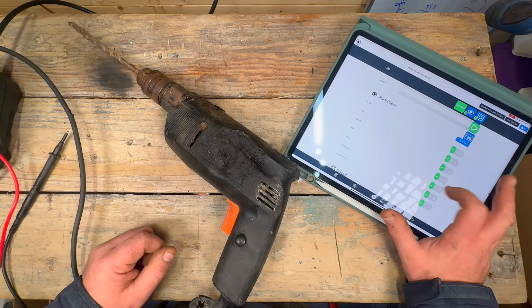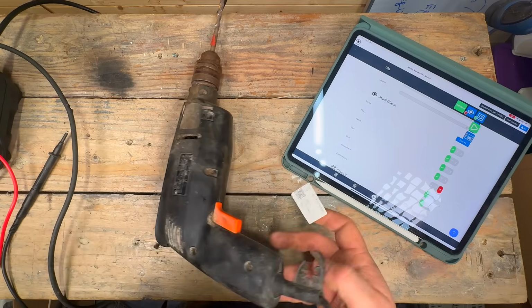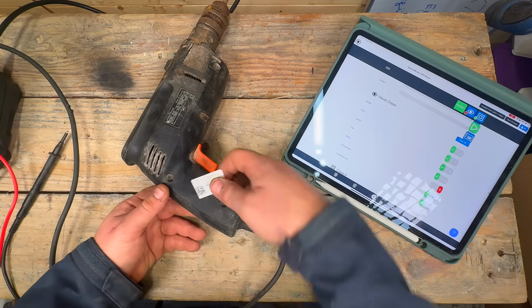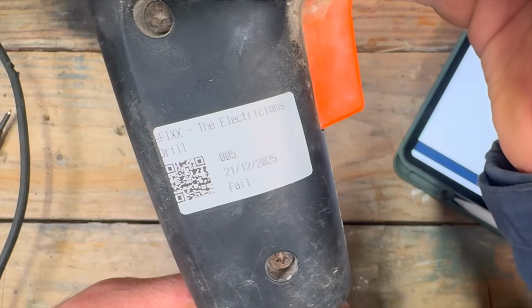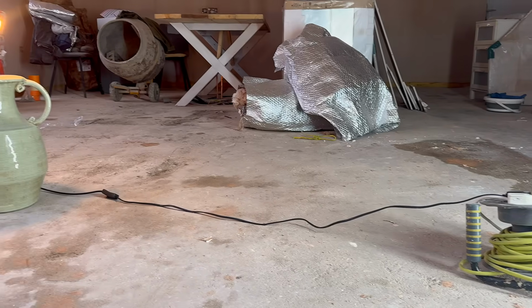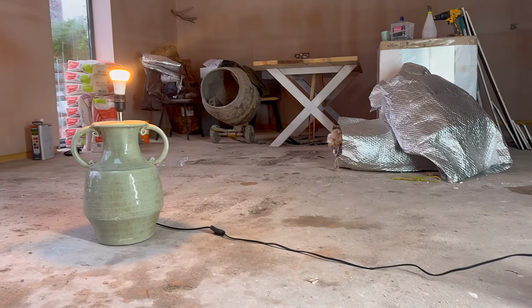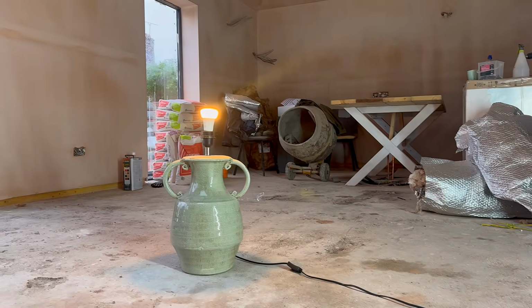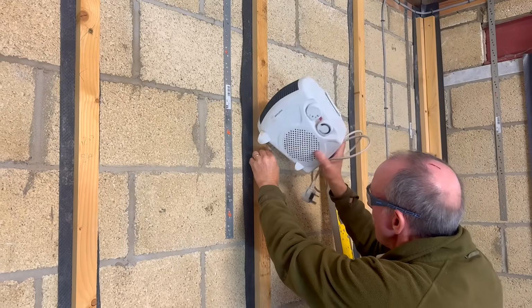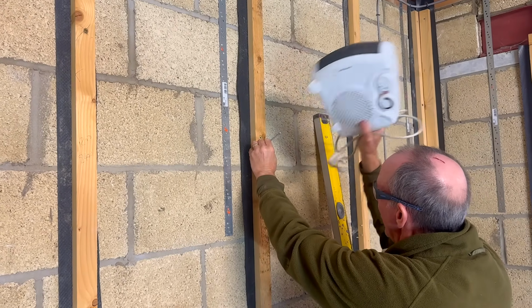If a fault is found, the equipment is switched off, unplugged, labelled so no one uses it by mistake, reported to the responsible person, and removed from service. User checks often stop a lot of equipment reaching formal inspection. They also highlight another point from the code. No amount of testing will compensate for equipment that is simply not suitable for the environment it is being used in. If it keeps getting damaged, the duty holder needs to replace it with something fit for purpose.